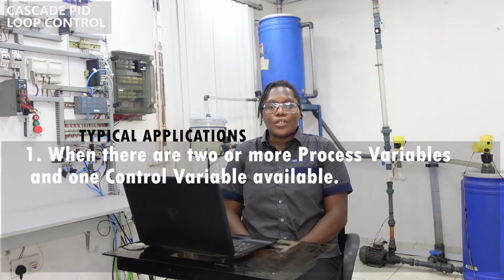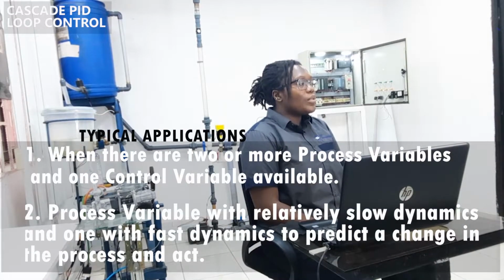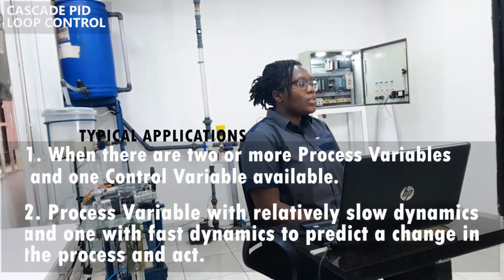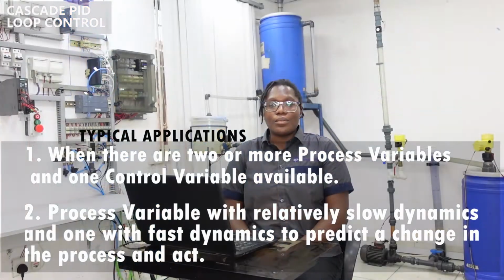When can Cascade control be used? It can be used when there are two or more process variables and only one control variable is available. It can also be used when you have a process variable with relatively slow dynamics and another process variable with relatively fast dynamics.